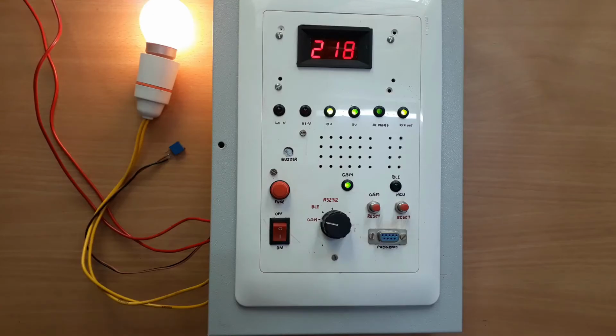Now the input voltage is reduced to around 220 volt. As you can see, our home town faces a lot of voltage fluctuation issues. So I have also increased the lower cutoff voltage up to 180 volt, because a lot of instruments are designed for a minimum voltage of 180. So our protection should be within that limit.